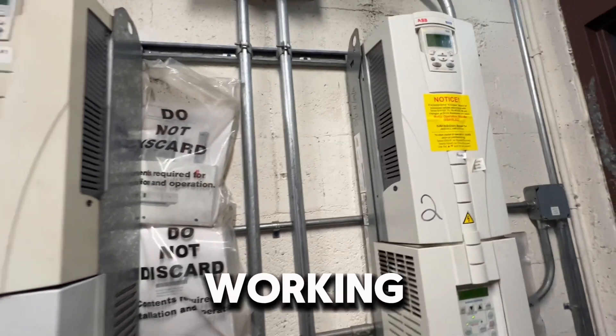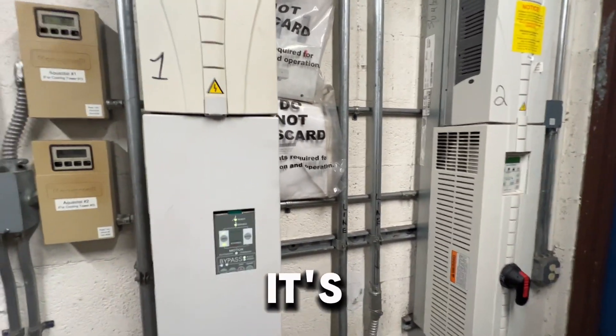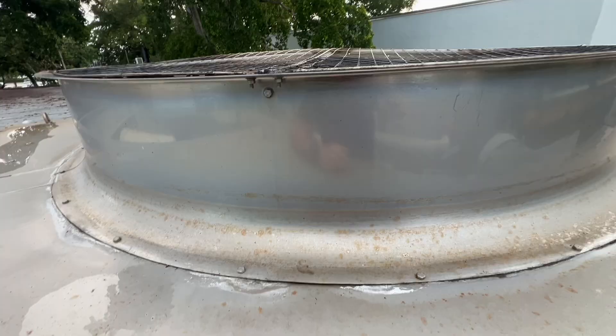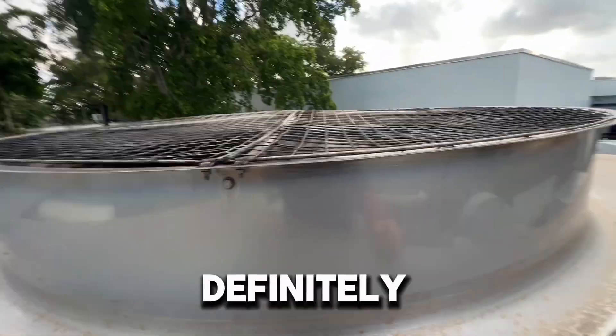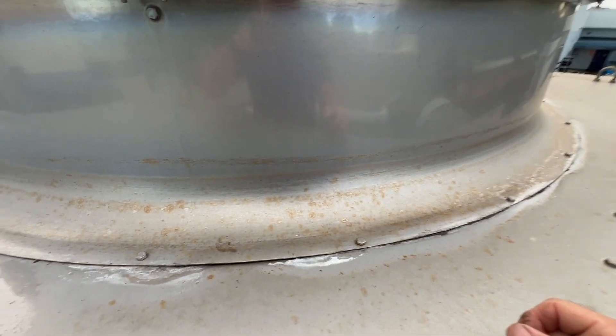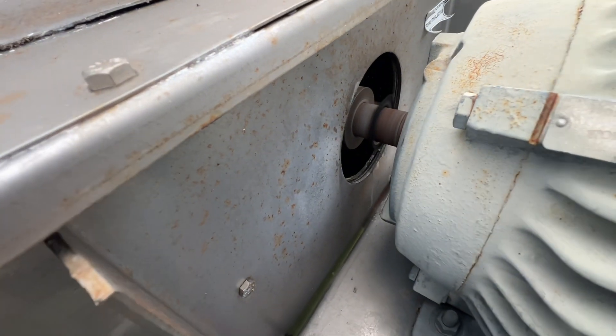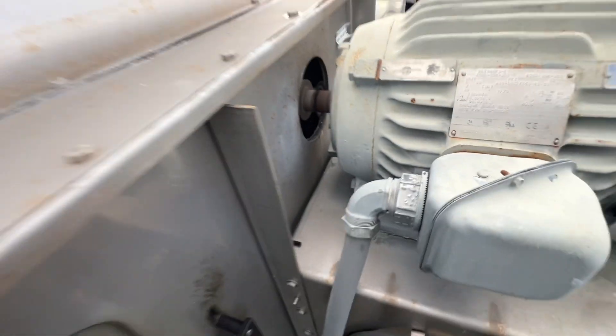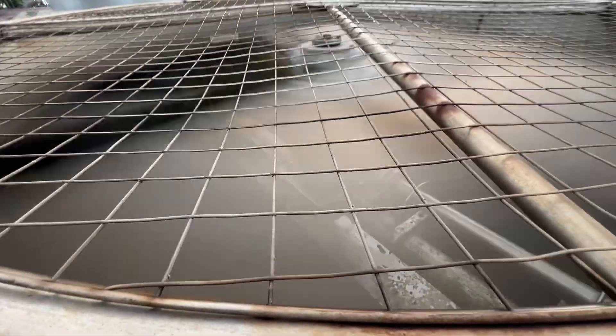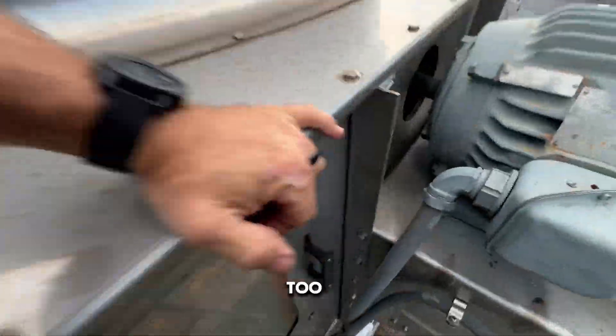Looks like we're working fine. We'll stay here a little bit, monitor it, make sure it's going to come down to temperature with no alarms. Looks good. The large towers are definitely no problem — these are shaft-driven. Nothing crazy. This one's running fine too.